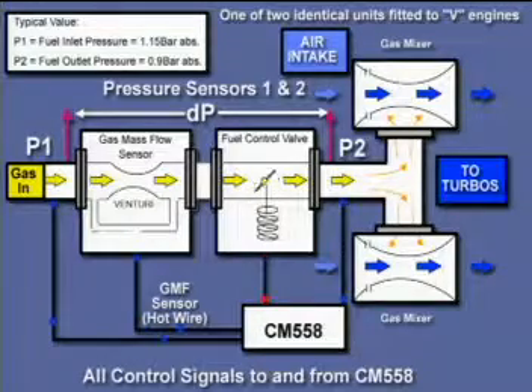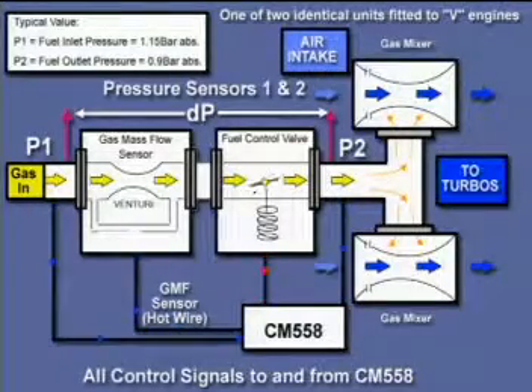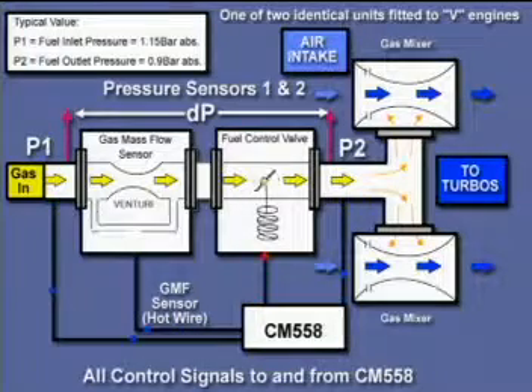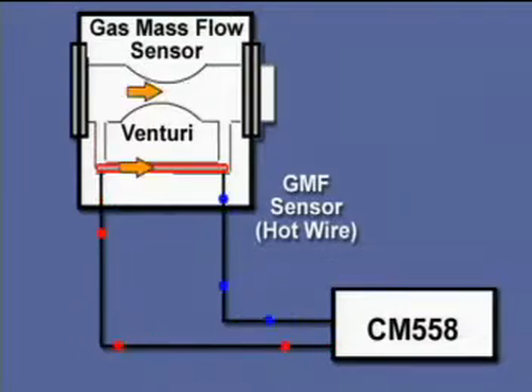The gas control assembly is controlled and monitored by the CM558. The gas mass flow sensor is a hot wire sensor. The CM558 sends a current through the wire, heating the wire. The natural gas flowing over the sensor tends to cool the wire and lower its resistance. By monitoring the change, the CM558 determines the quantity of gas flowing. Positioning the sensor in the bypass passage provides less turbulent flow over the sensor and improves resolution.